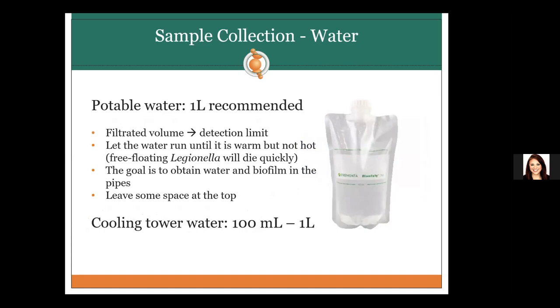For water collection, it's recommended to get at least one liter for potable clean water. The amount of water provided will determine the detection limit of that sample. Let the water run until it's warm but not too hot, as heat could potentially kill any Legionella and give false negatives. The goal is to capture the water and any potential biofilms inside the piping. For cooling towers, the recommended volume is between 100 milliliters and one liter. We sample less for cooling towers because they tend to be non-potable, meaning more bacteria is present and you don't want to overload the filtration process.